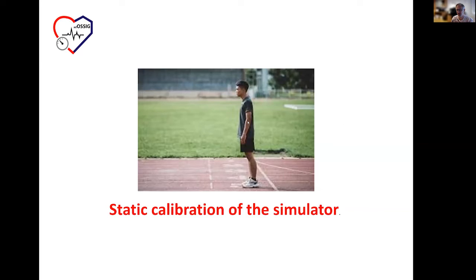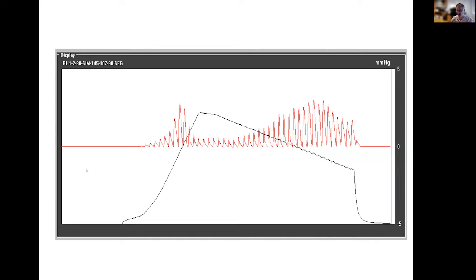And if I put all this together into one picture, this is how this looks like. So the red curve here is what the simulator is producing. So this is the output of the simulator. So basically, when the cuff pressure goes up and then deflates, at a certain point, these pressure pulses start to grow. And the largest, the highest pressure pulses are here, which correspond to these higher peaks here. And then later on, the pressure pulses go down, and then the device completely deflates and the pressure pulses are gone. What you can see from this picture is that the simulator actually produces the pressure pulses twice, once here and once here.